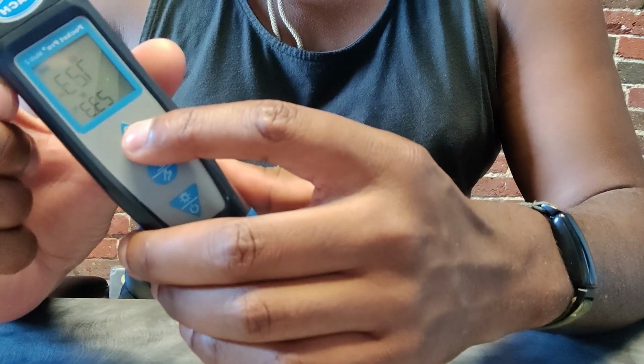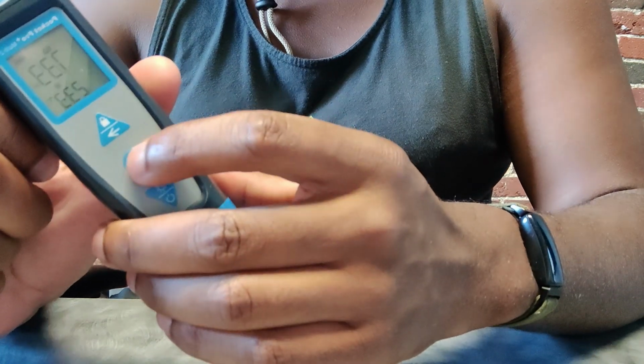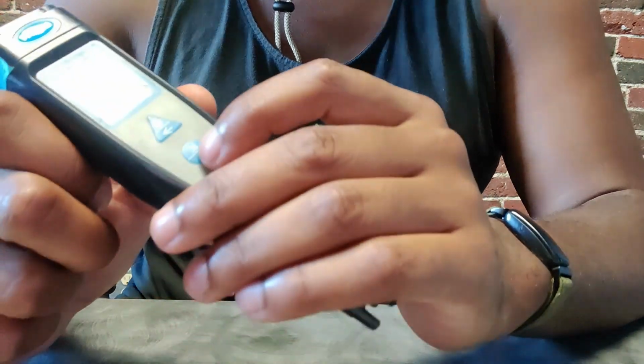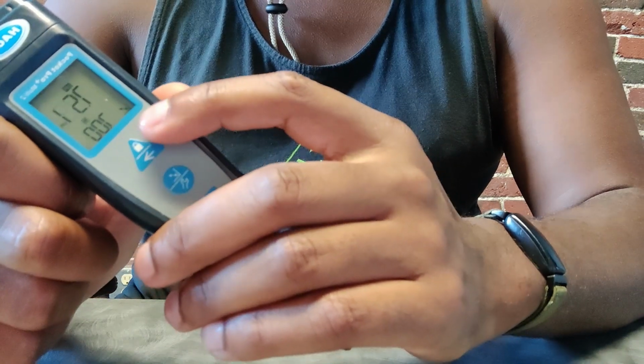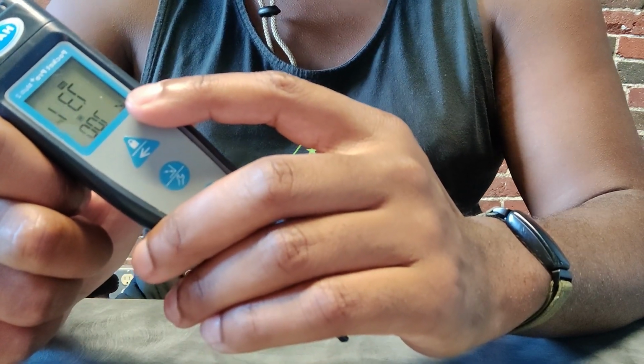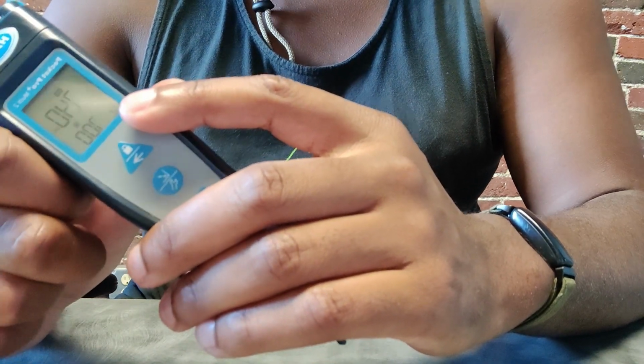Press and hold the top button to change the Hach's parameter to pH. Then press the middle button on the Hach to enter calibration mode. You should see a small graph in the left corner of the screen to confirm that the Hach is in calibration mode.